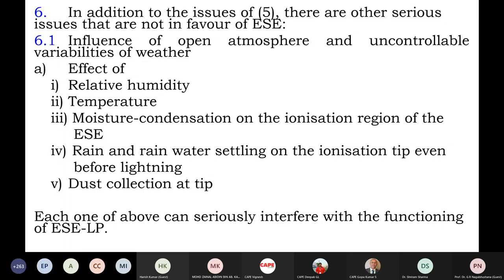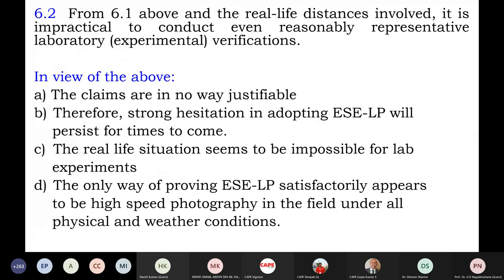Remember, the ESE rod is supposed to be placed in the open atmosphere, either on top of a building or in an open field protecting large areas. But what about the influence of the uncontrollable, enormous variabilities of the weather: the effect of relative humidity, temperature, moisture condensation on the ionization region of the ESE, rain and rainwater settling on the ionization tip even before lightning, dust collection at the tip? So what are the effects of these parameters on which we have no control? Each one of the above can very seriously interfere with the function of the ESE LP, whereas a normal Franklin rod is not subject to these at all. So the behavior of that will be more consistent than that of the ESE. But we have to see the performance of the ESE rod under various weather conditions, first of all.